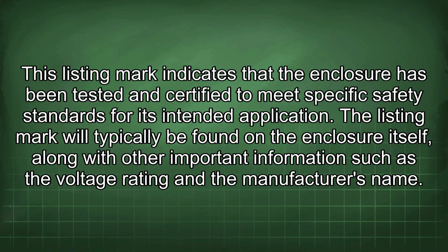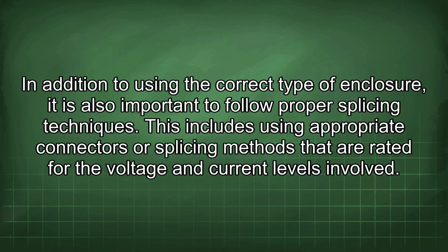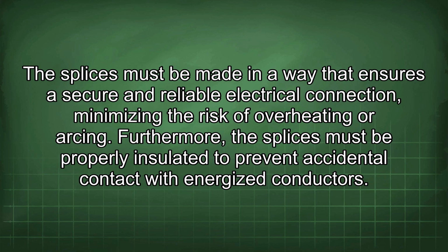This listing mark indicates that the enclosure has been tested and certified to meet specific safety standards for its intended application. The listing mark will typically be found on the enclosure itself, along with other important information such as the voltage rating and the manufacturer's name. In addition to using the correct type of enclosure, it is also important to follow proper splicing techniques. This includes using appropriate connectors or splicing methods that are rated for the voltage and current levels involved. The splices must be made in a way that ensures a secure and reliable electrical connection, minimizing the risk of overheating or arcing. Furthermore, the splices must be properly insulated to prevent accidental contact with energized conductors.